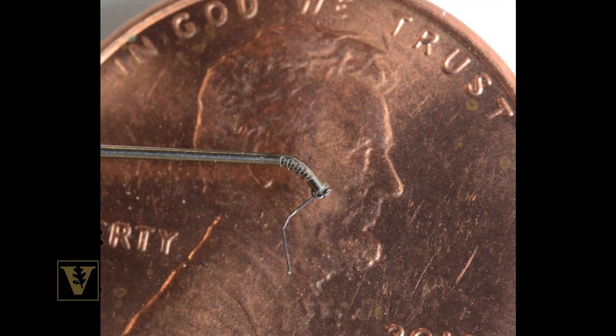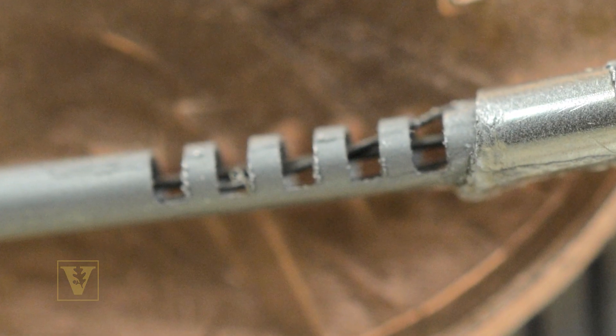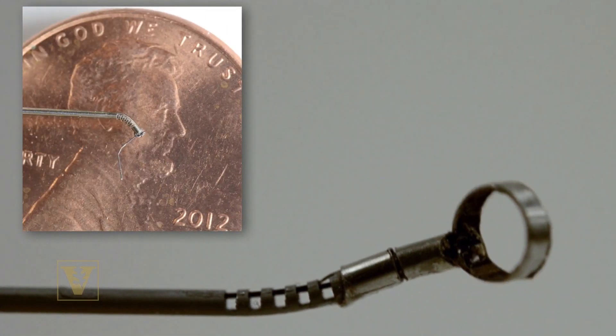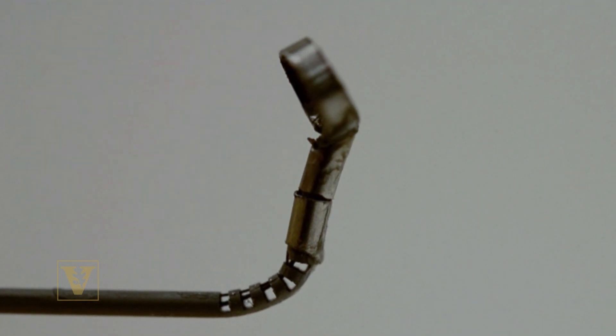We basically take a very small tube that's the size of a needle, and we cut little notches in the tip. We run one wire down the inside of the tube, and we pull on the wire and that makes the tip bend. What it does is it gives the surgeon a little bit of ability to turn a corner at the end of the tool.